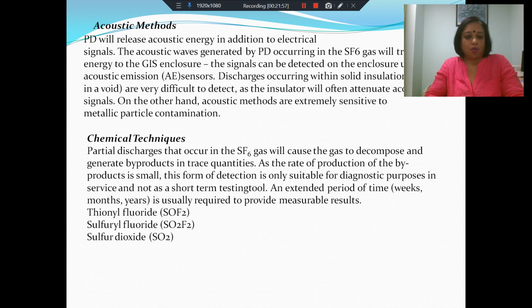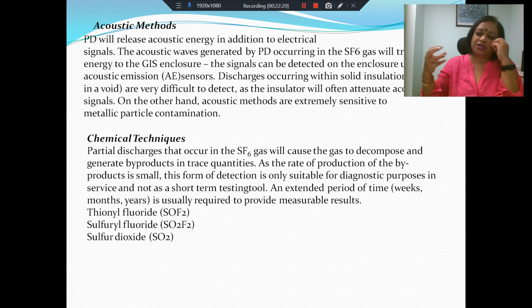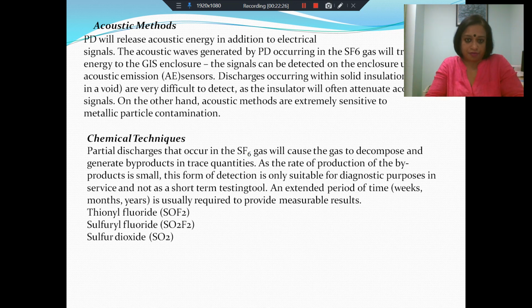When partial discharges occur in the SF6 gas, the gas will decompose and they will generate byproducts. So in a manner similar to the dissolved gas analysis that we have discussed in the context of transformers, we can use chemical techniques where you try to figure out what is the percentage of a particular byproduct within the gas. So again, you would have some kind of gas extraction means, and then you would need some chromatographs. As the rate of production of the byproducts is very small compared to, let's say, in a transformer, you cannot use this as a continuous, you cannot use this as a short-term testing tool.